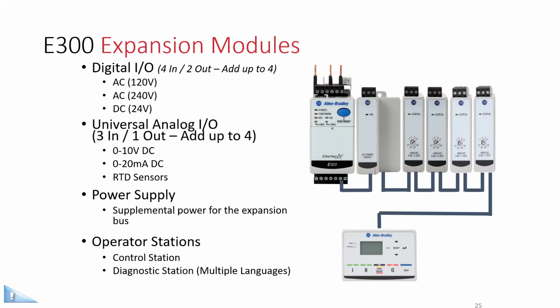On the universal analog, there's 0 to 10 DC, 0 to 20 milliamp DC, and RTD sensors that are also available. Operator station, like I said, it will do multiple languages, but it fits into a standard 22 millimeter hole. So you can put this down the line a little bit, and you can configure it all just with the operator station. Or it's got like the local remote handoff. You can program that to do the function.